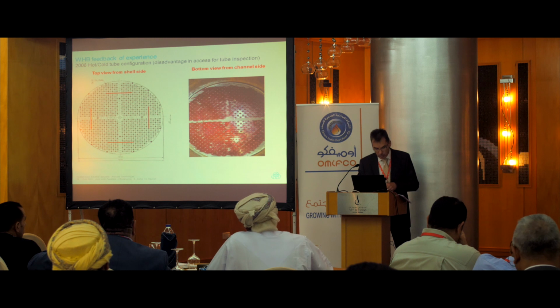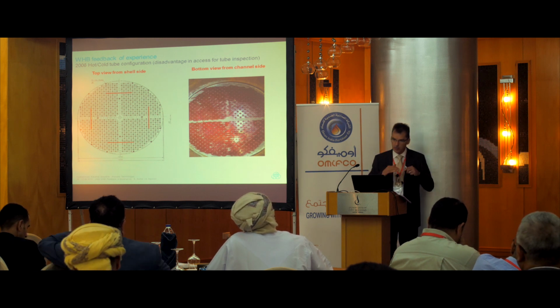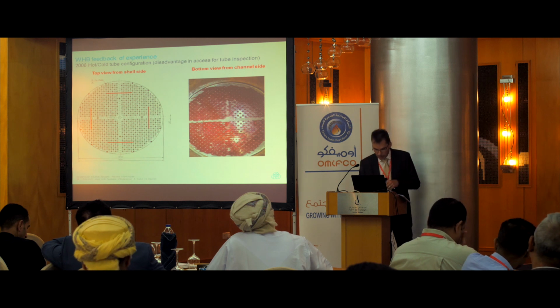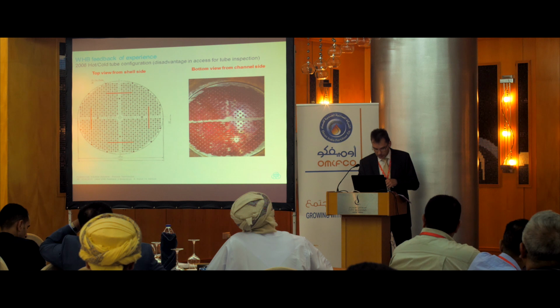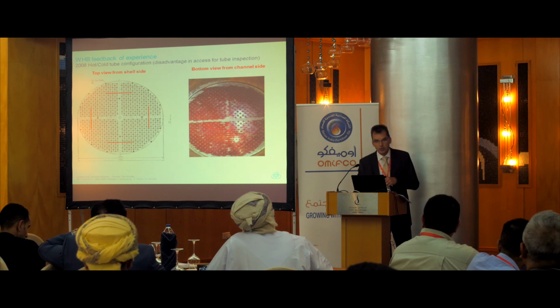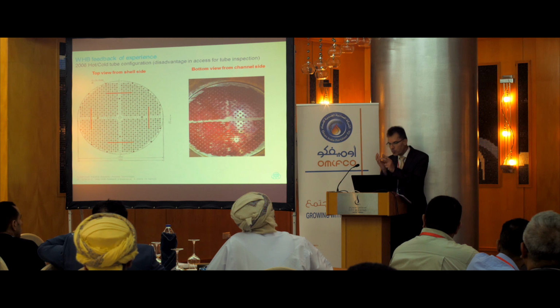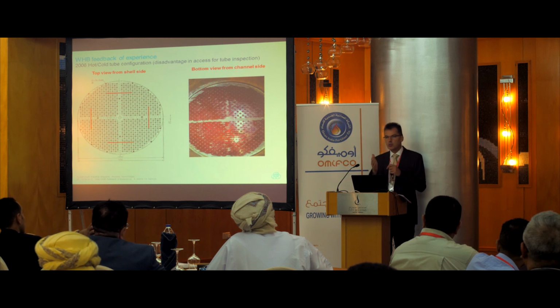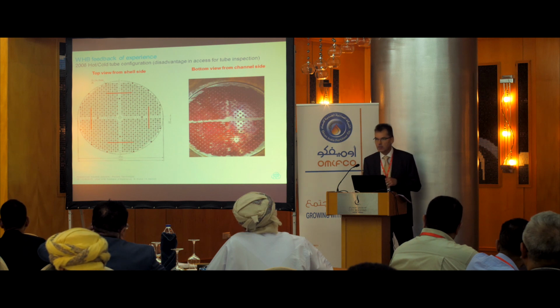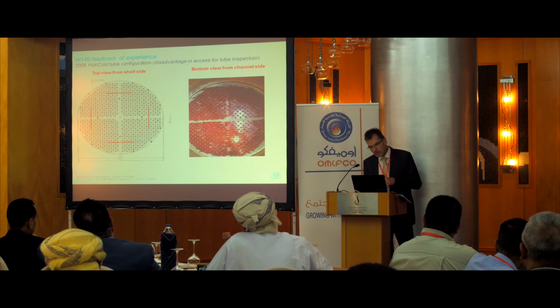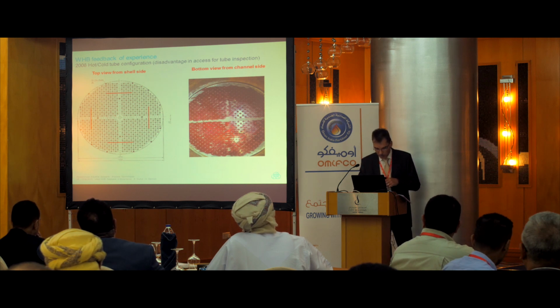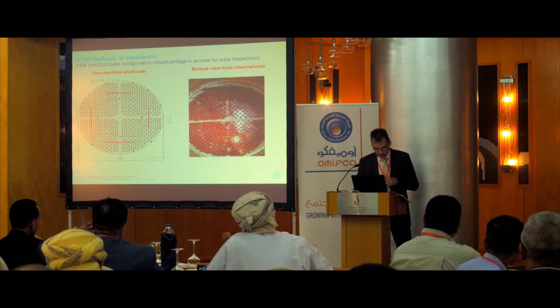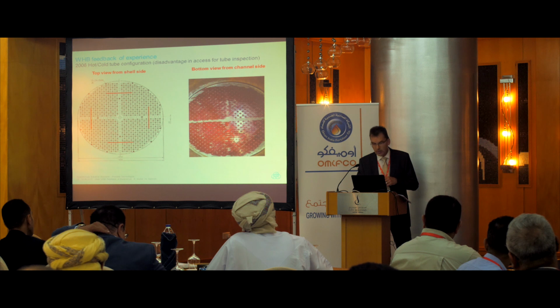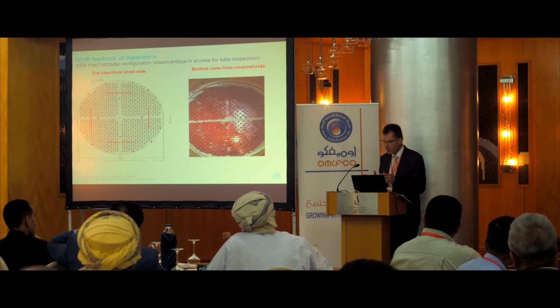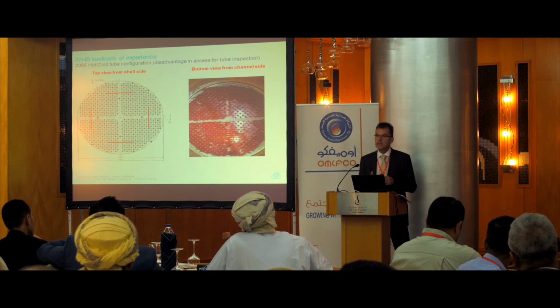Why? This is due to the fact that the so-called false tube sheet, you remember, we have had these hot internal channels, which is below the tube sheet, covers the cold return tubes. And therefore, we are not able to check the cold tube side. This can only be done if you drill holes in this false tube sheet to have an opening to see the hot cold end of the U-tube and to go in with an eddy current testing device, ultrasonic testing device, and so on. We made the procedure also to do it without cutting a hole. That means you do a helium leak test to identify the location of a defective tube, and then you know exactly where you have to drill a hole, but this is time-consuming and not really a good idea.